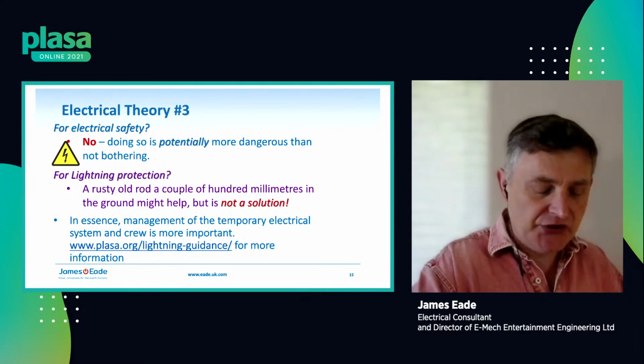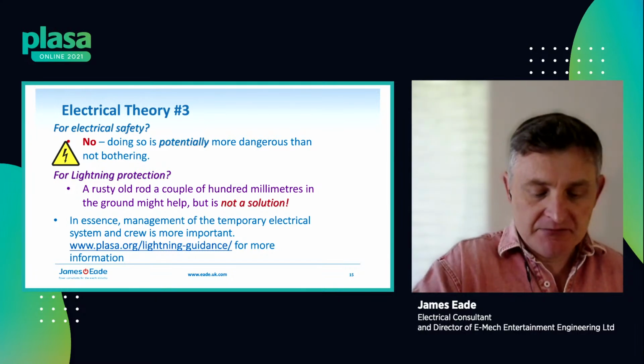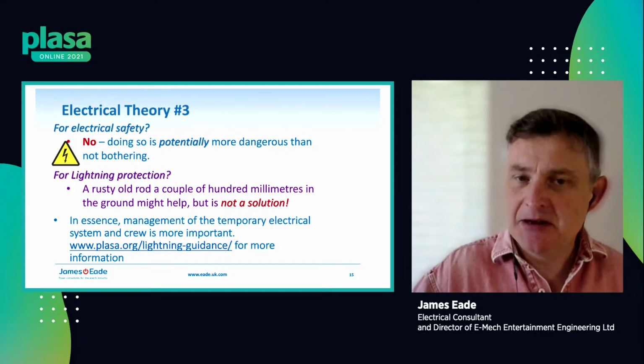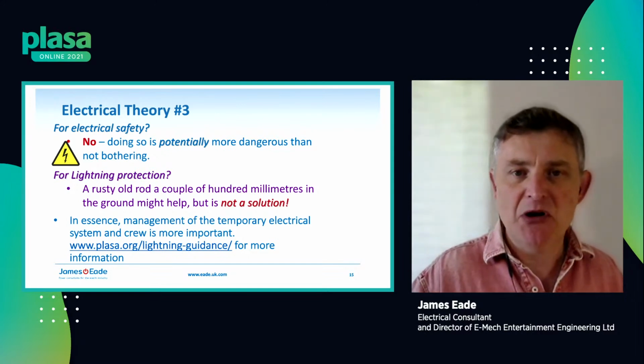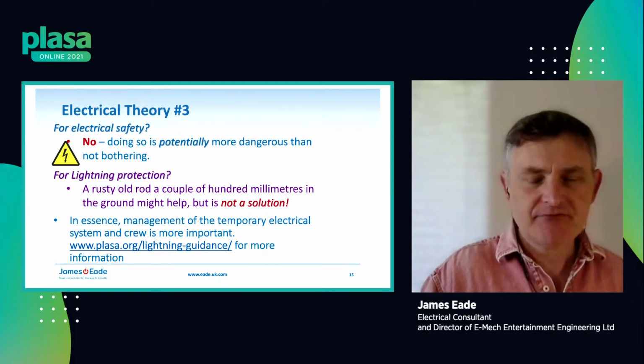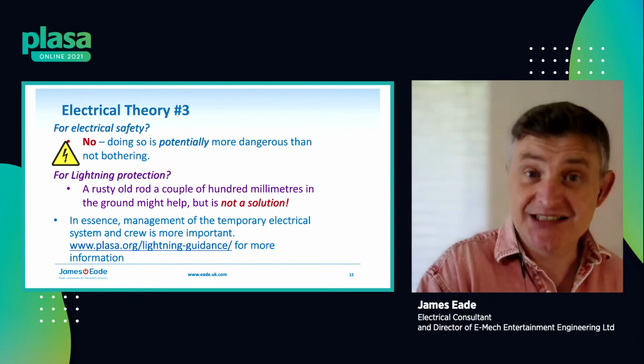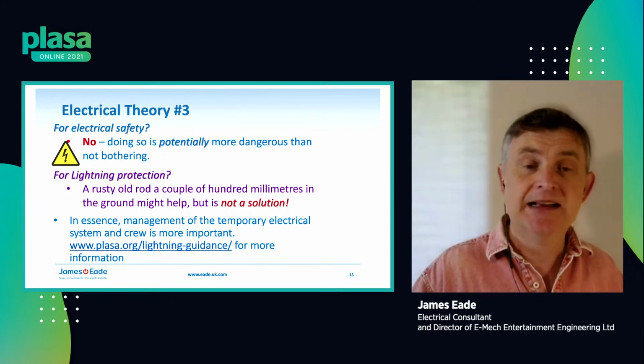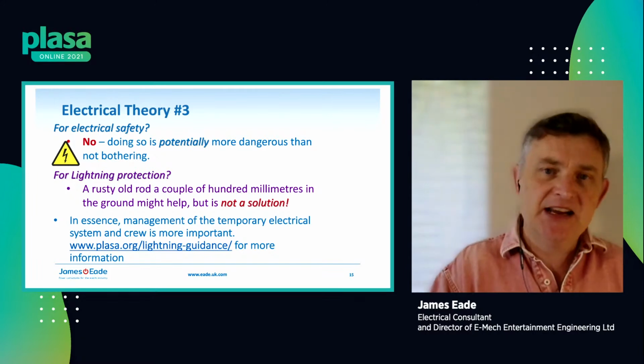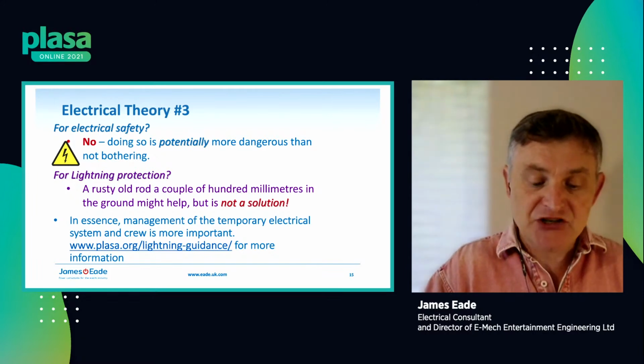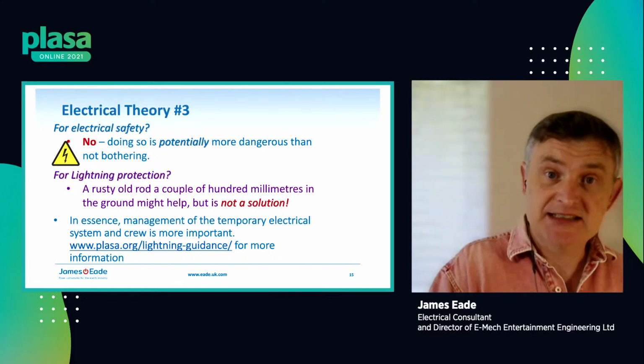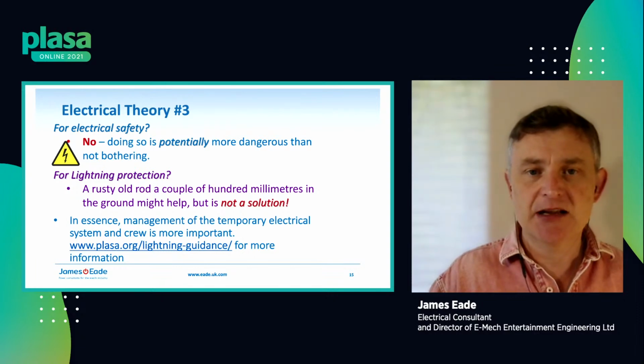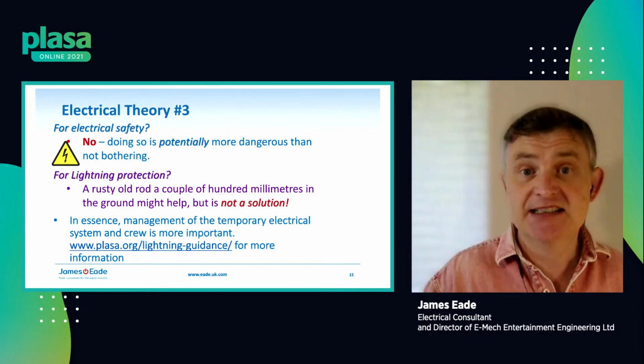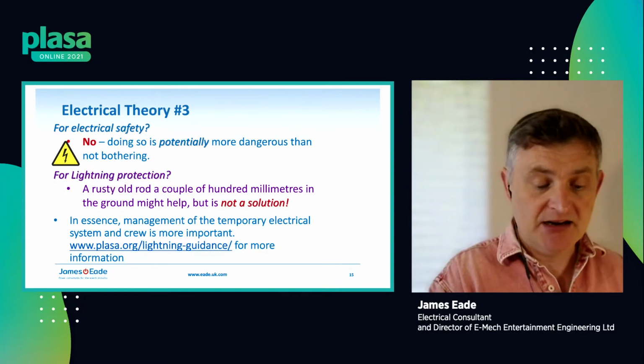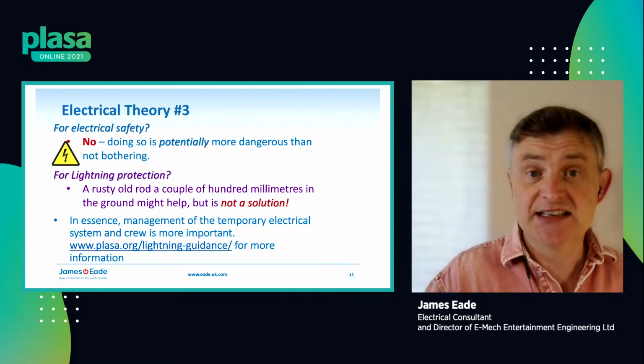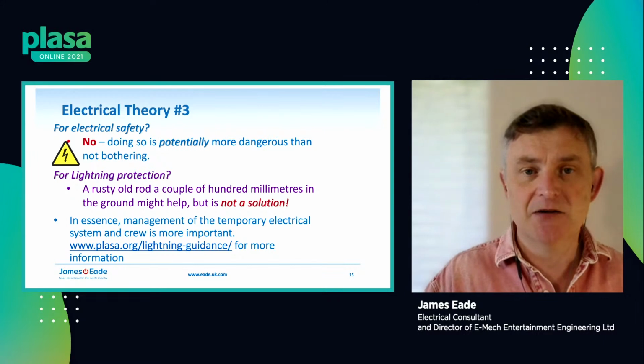Trying to do that by putting an earth rod in at the tower, expecting it to find a reliable path back to the earth rod at the generator, is more likely to be hazardous than doing nothing at all. For electrical safety you need to connect the tower properly to the earthing arrangements of the supply. A good example is to take a protective conductor connection off the distro that's powering the tower itself.